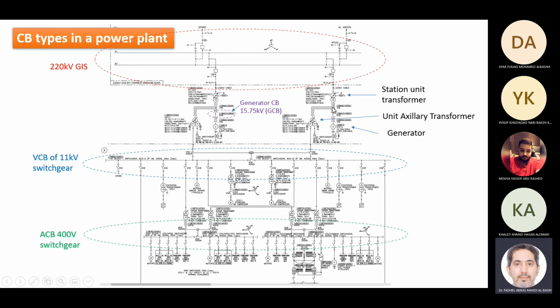Now the output of the generator can also be connected to another transformer, like a 3-winding or 2-winding transformer, to step it down to a lower voltage. So this is like from 15 kV, for example, it can go to, let's say, 220 kV. This is the 220 kV circuit, the feeder or transmission line. It has a breaker and an earth switch, where you connect during service maintenance. You disconnect the breaker, and you ground this circuit so that it is safe to operate during maintenance.